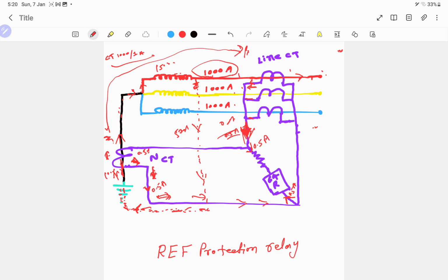Because the direction of the line primary current of the neutral CT is towards the winding, the secondary will flow in the opposite direction, like this. And now there is 0 amp here, no ampere, because of the balanced load here. There is no amp flowing this way, and hence only the 500 amps of fault current is creating the 0.5 amp of secondary neutral CT current, which will come here. Because this is a balanced load and it creates the high impedance, the current will not go through the high impedance, so the current will flow through the relay.